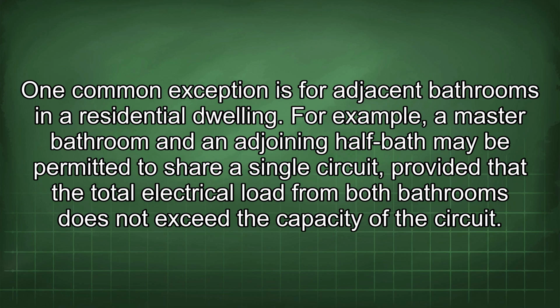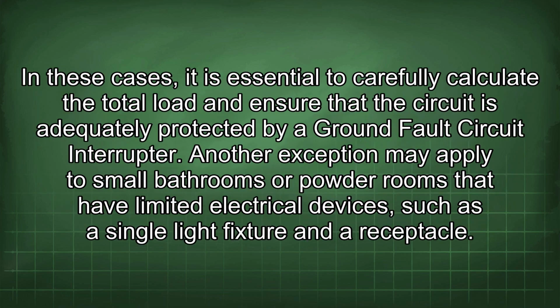For example, a master bathroom and an adjoining half-bath may be permitted to share a single circuit, provided that the total electrical load from both bathrooms does not exceed the capacity of the circuit. In these cases, it is essential to carefully calculate the total load and ensure that the circuit is adequately protected by a ground fault circuit interrupter.